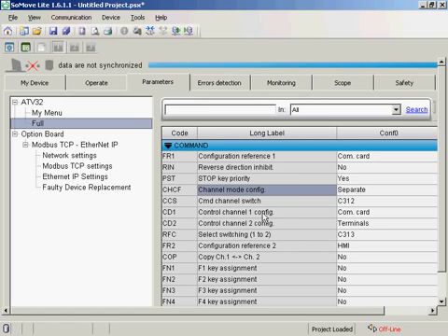The command word is going to be based on the 12th bit of the control word, and if that bit is 0, we're going to use the COM card. If not, we'll use the terminals. The reference switching will be based on that 13th bit. We're going to control the reference speed via the COM card or via the HMI on the ATV32.